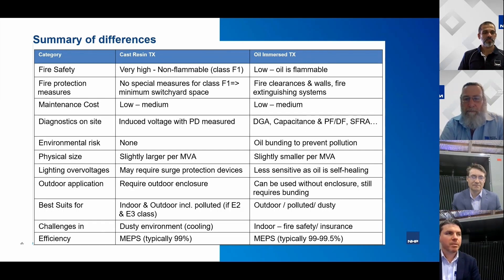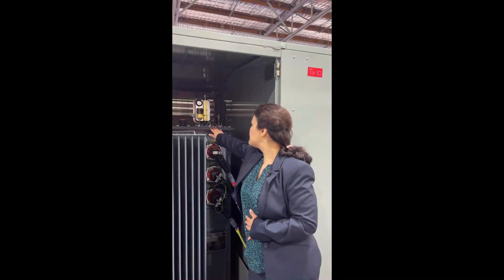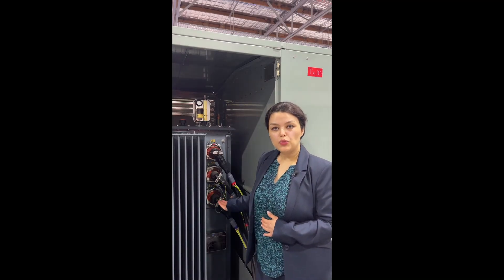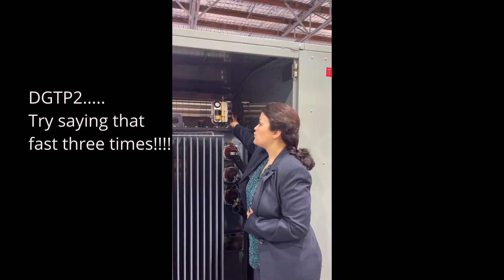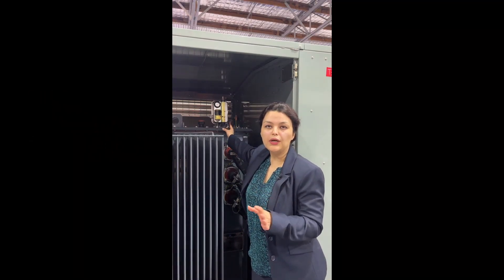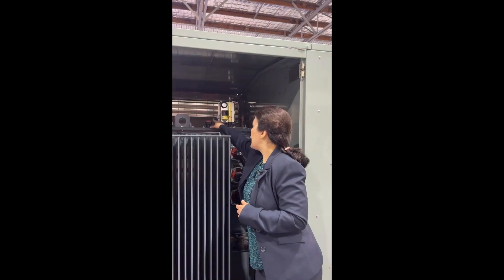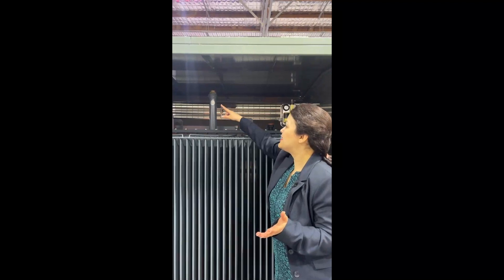We'll now cross over to Shabnam to take us through the physical construction of an oil transformer on display in the power hub. What we have here is an oil tank, HV terminals using plug-in bushings with screened elbow connections, cooling fins, and the DGPT2 integrated protection device monitoring temperature, pressure, and oil level. There's also an offload tap changer, a welded lifting point, a safety valve, and an LV cable box.